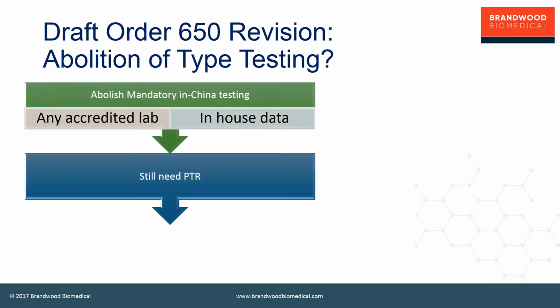However, you still need a product technical requirement. That's the document which drives the testing, defining all the specifications and performance requirements for the device, and that's what you test against. It's based on the current Chinese standards. You still need to have that document, and it will still need to go into your registration submission. You need to have your test laboratory, wherever you choose to do this, test against the PTR.